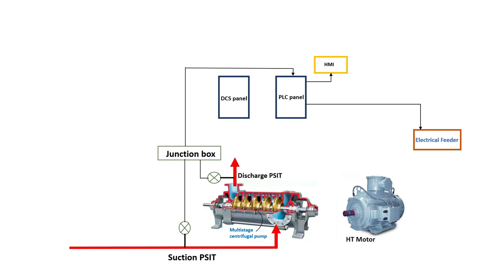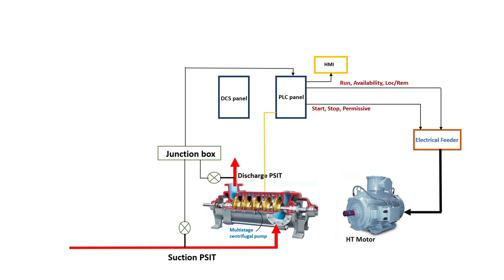We have different digital output signals like start, stop and permissive going to the electrical feeder. At the same time, we receive digital input signals from the electrical feeder — those control signals include run feedback, availability, and local/remote indications. These are the different control signal loops between the PLC and the electrical feeder. The electrical feeder in turn powers up the HT motor.